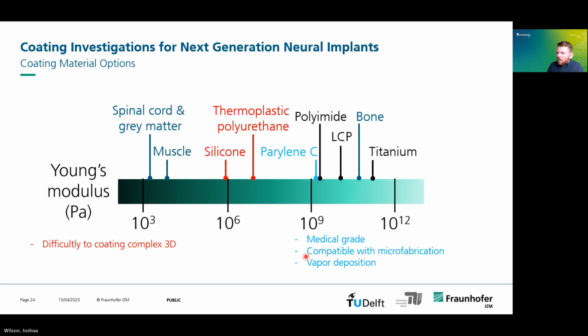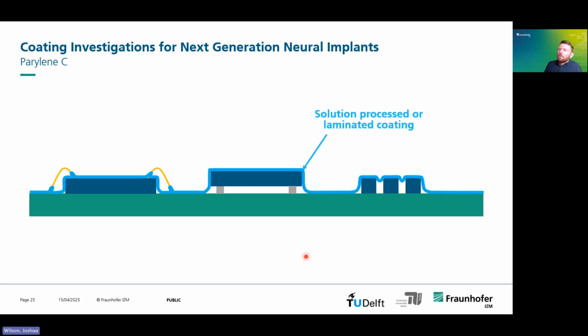So to explain the detail of this, effectively, if you were solution processing or laminating a coating on your system where you have wire bonded components, or however you were assembling your components on the surface, what you find, and this is slightly exaggerated, is you don't have perfect coverage. You have some voids. You can't get underneath structures if there are gaps. If you have very fine pitch, then you can have this tenting, and then there are more voids. And anywhere there's voids, this is just a space for the body fluid to get in and start the corrosion process. So this is really a major point of failure.